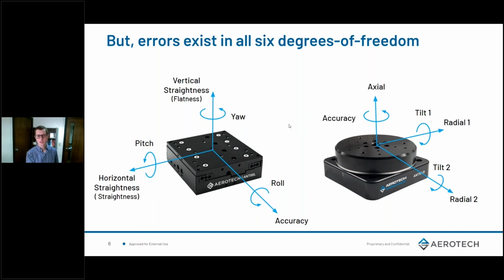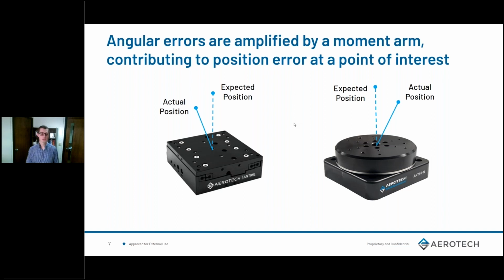These off-axis rotational errors are especially important to understand, because they contribute to large errors at your work point. If you look at the linear stage on the left-hand side, you'll see the expected position. This is the position that you would expect your optical probe to end up in. Let's say your optical probe is at that point. You make a linear move. You would expect to move along a line and potentially have an accuracy and repeatability error on that line. However, because there's an offset between your encoder, which is in the stage, and the physical probe position, which is at that expected position, this offset amplifies the angular errors. If there's a roll or a pitch of the stage as you're moving in the direction of motion, that manifests as a translational error at the work point, amplified by the moment arm from the encoder read head to your probe position. So instead of ending at the expected position, you may end up at the actual position.